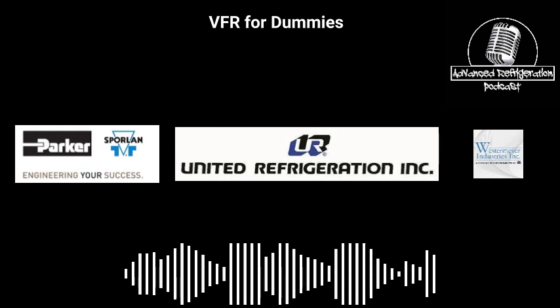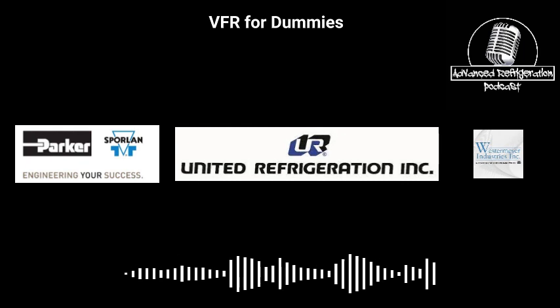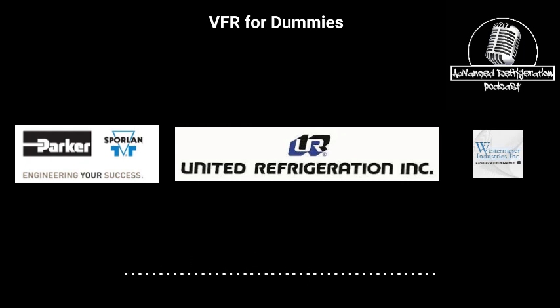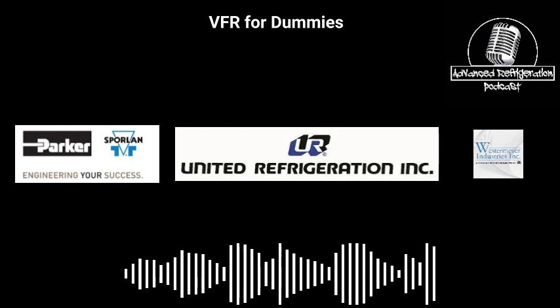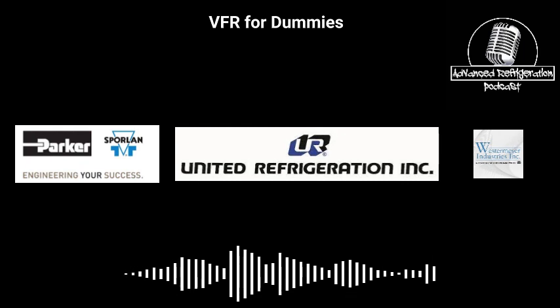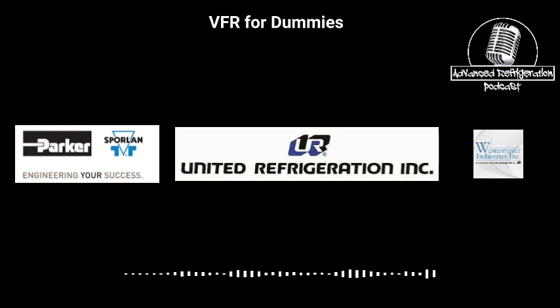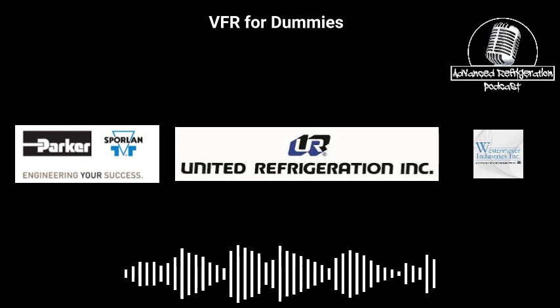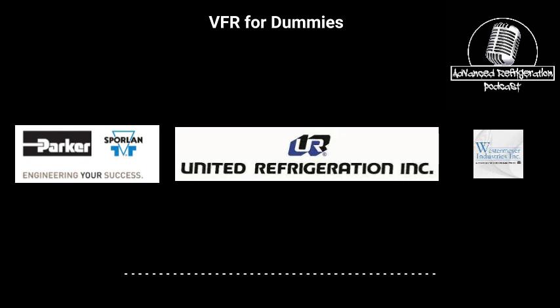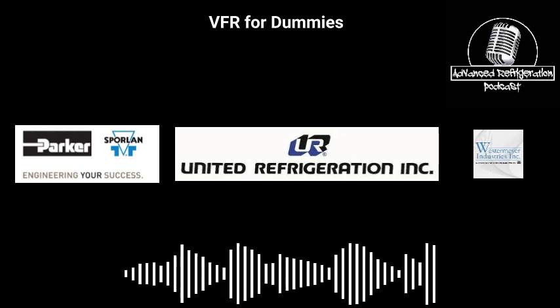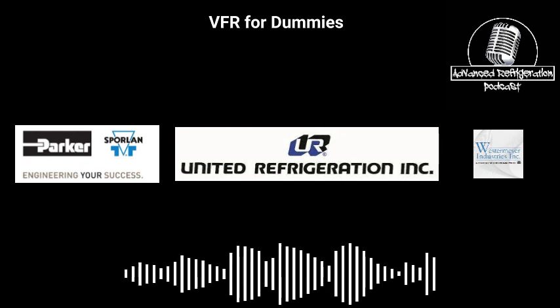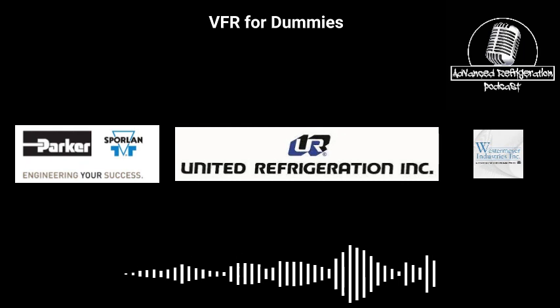Yeah. Really? I mean, looking at this from our perspective, from a refrigeration side, this seems like a recipe for dead compressors. Oh yeah. He's not disagreeing. No, because there's so much piping and so much room for error, the install really has to be perfect for it to have minimal problems. In the 8 years I've been out here, hundreds of compressors have failed. Sure, I'm not going to deny that. The systems that are installed well have far fewer issues. When I say well, I'm saying care for piping practice, purging when you're brazing, straight pipes that don't wave all over the place, traps like I was mentioning earlier. Things like that really go into making sure the install is good.